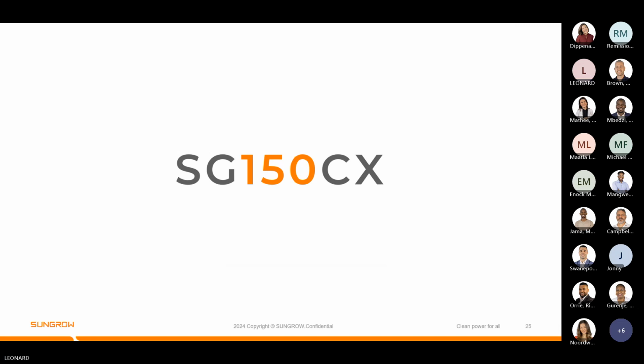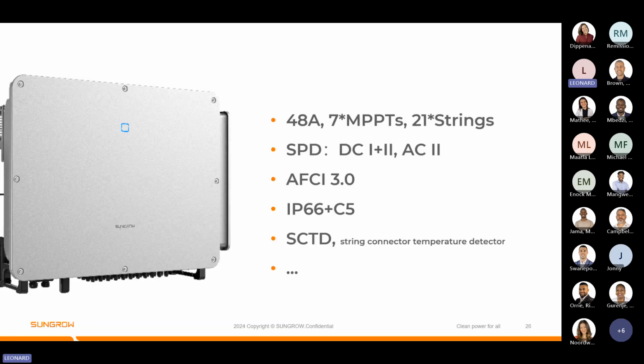Then also we're planning to release the 150 CX, SG150CX. So this will be a 150 kilowatt stringing solution. This will allow for 48 amp per MPPT, 7 MPPTs, and 21 strings. The reason for decreasing the MPPTs is due to the actual MPPT losses. So that's the reason why we went for 7 MPPTs, and we increased the MPPT current to 48 amps.